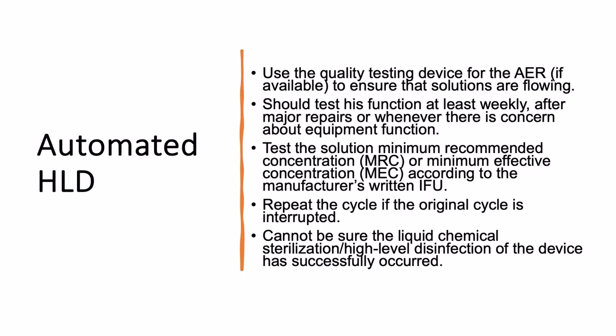For automated high-level disinfection, use the quality testing for the AER that you're using. You should test this function at least weekly, after any major repair, or whenever you have a concern about the equipment's function. You should test the solution in the AER for the minimum recommended concentration or minimum effective concentration according to the instructions to make sure the solution is still strong enough to give you high-level disinfection. Repeat the cycle in the AER if the original cycle is interrupted because you can't be sure the liquid chemical sterilization or high-level disinfection of the device successfully occurred.